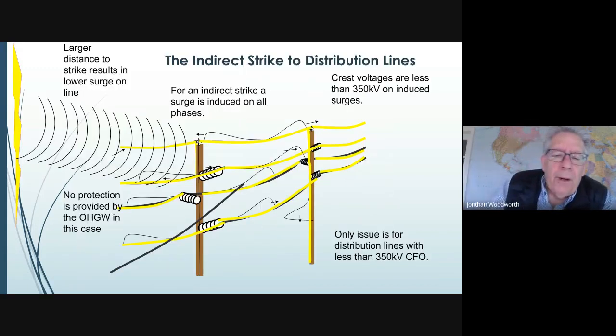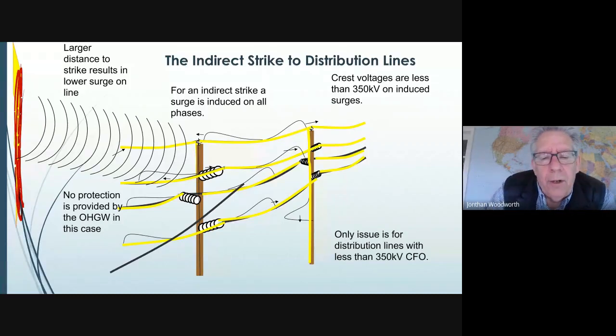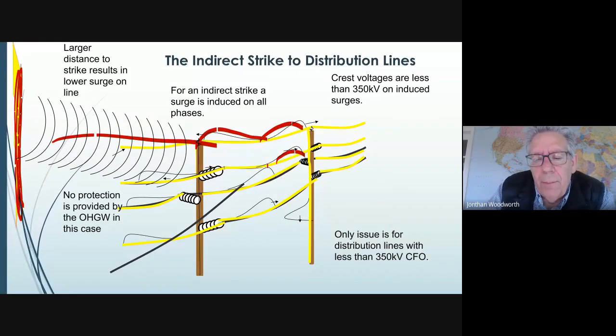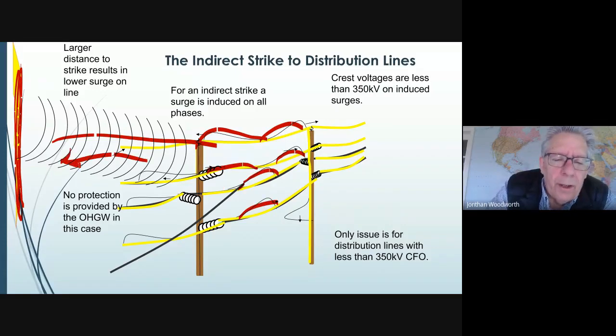Another important aspect of lightning is that it doesn't always hit the lines directly. It might hit 100 meters or 200 meters away to the left or the right. When it does that, it does put a surge on the system, but luckily the surge is much lower, and the farther away you get, the lower that surge is. This is called an indirect strike, as opposed to a direct strike, which we were talking about earlier.